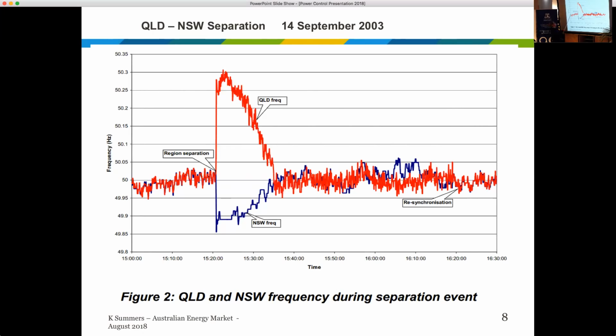And here's 50, this is 50.05 and this is 49.95. And here we are sitting there - separation event occurs, overgeneration in Queensland, high frequency, takes a few minutes, about 10 or 12 minutes to get back to here, and it takes a fair while to wrap back up here. But look at where it comes back to.